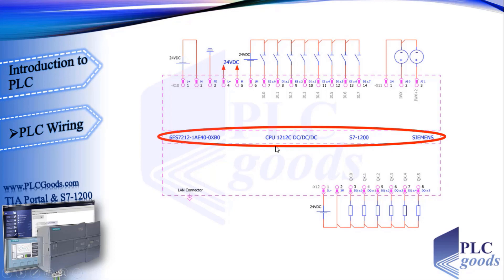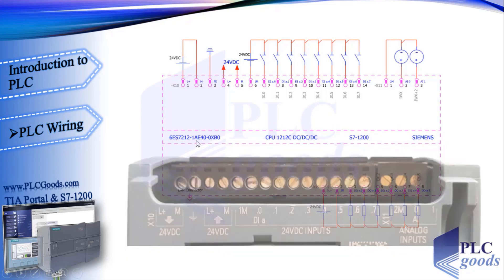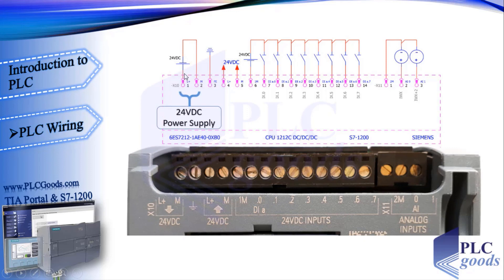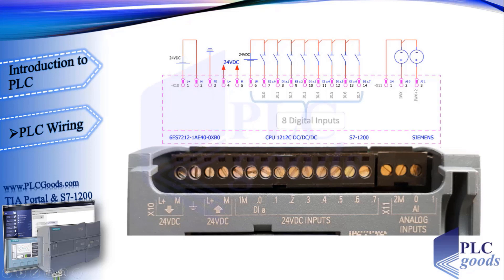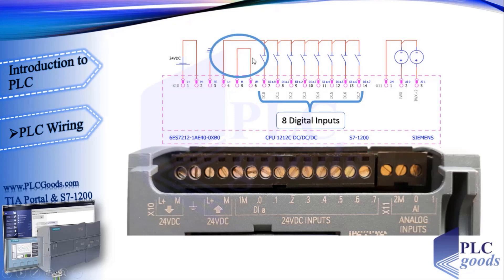This is a simple wiring of my CPU with this information. Wiring of the CPU and others is pretty much the same, but we advise reading the manual carefully for each device. First, the CPU needs an external 24-volt DC power supply to work. We will use the internal 24-volt DC to power digital inputs.